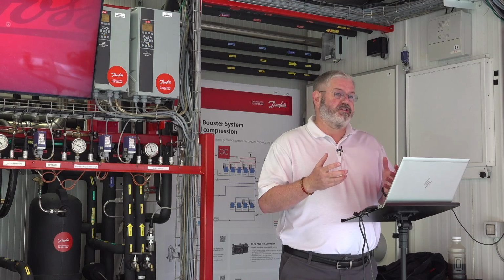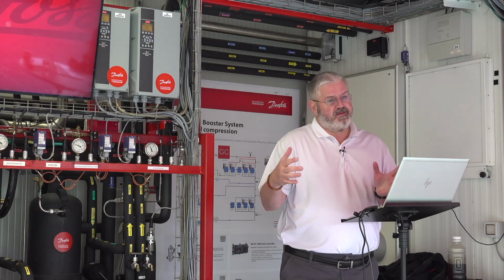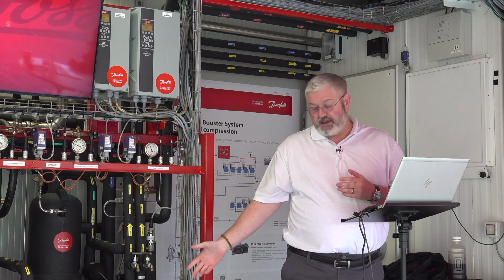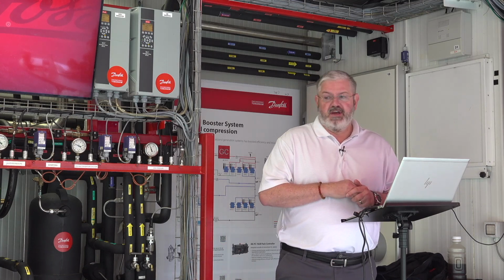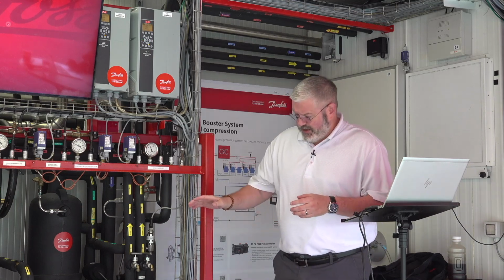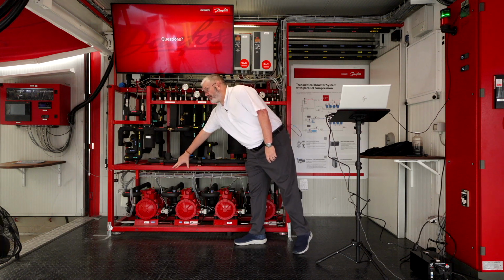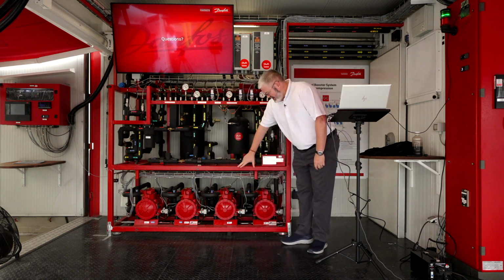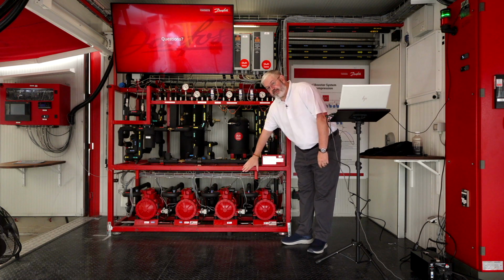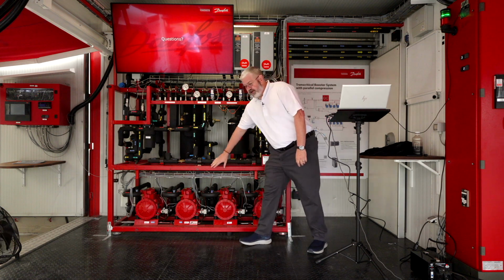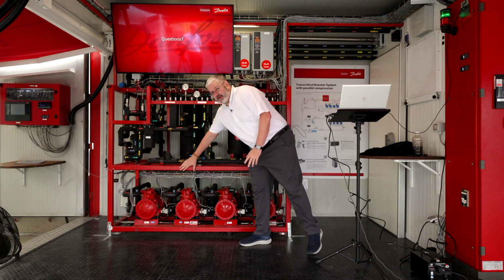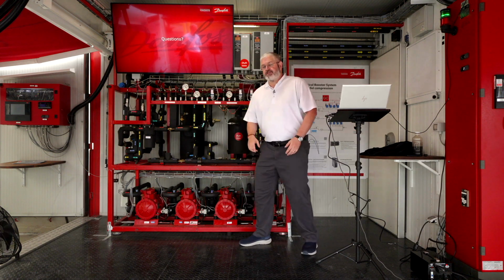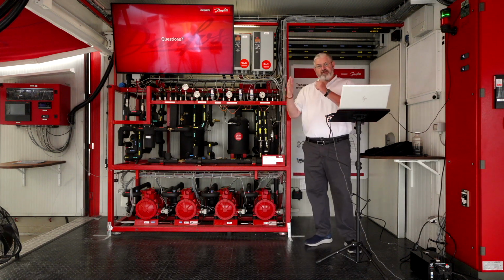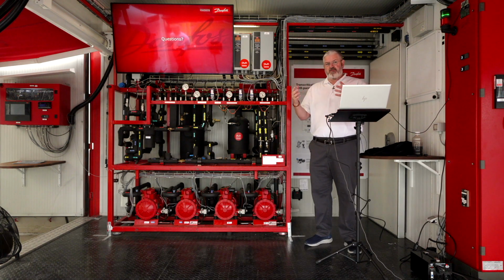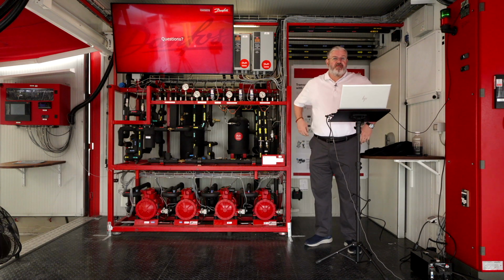Much in the way that when you start a system up, you charge the system, you get medium temp loads running first so that your compressors are running, because they're kind of the condenser for your low temp compressors. But for that example, let's assume on the left here, if we could switch to the unit view, let's assume that our parallel compressors here were low temp discharging into these two at medium temp. If the medium temp, for whatever reason, shuts down completely while low temp is running, our software shouldn't let it do that. But if it did, these would quickly trip on their high pressure switch, because basically they would get a stop into the medium temp suction, quickly build pressure, and trip on the safety switches. So they would shut down on switches.